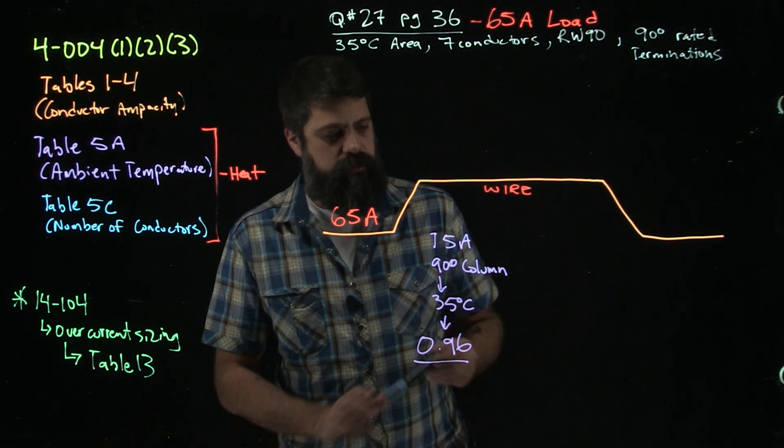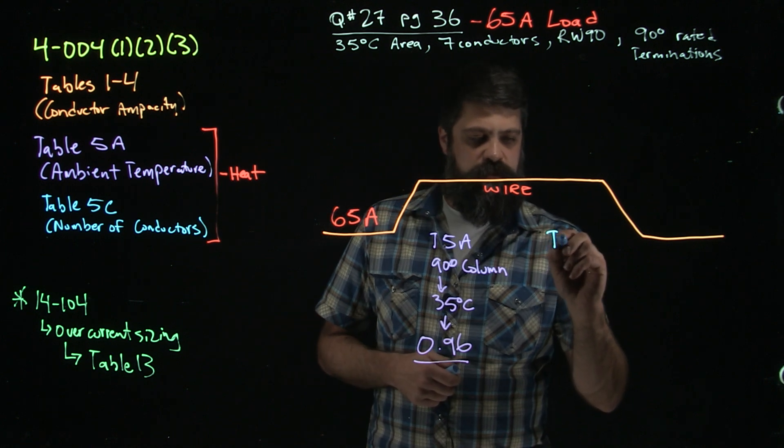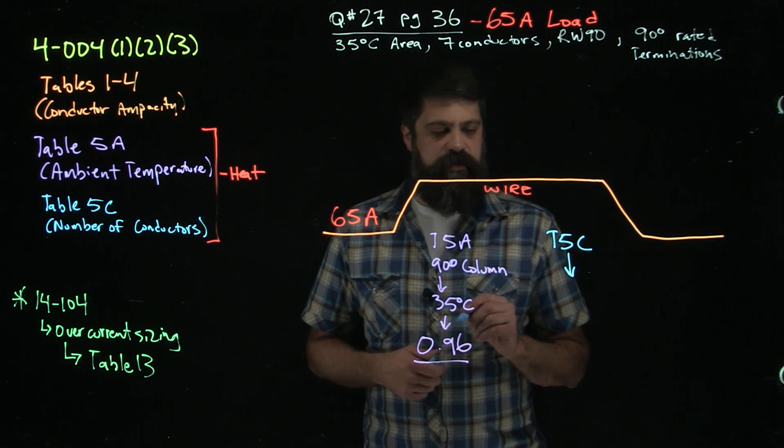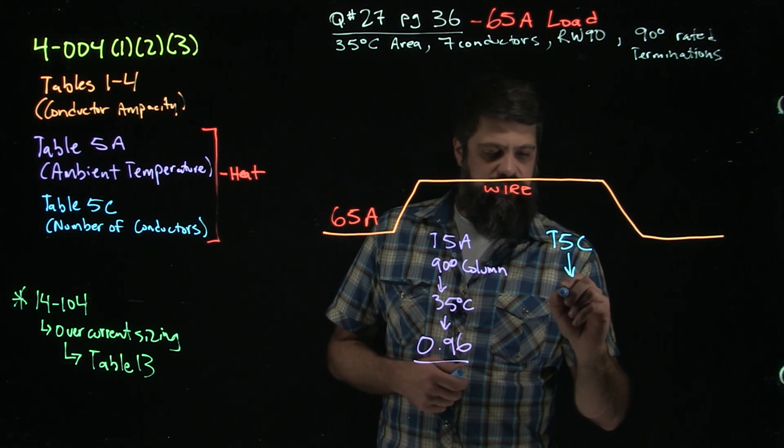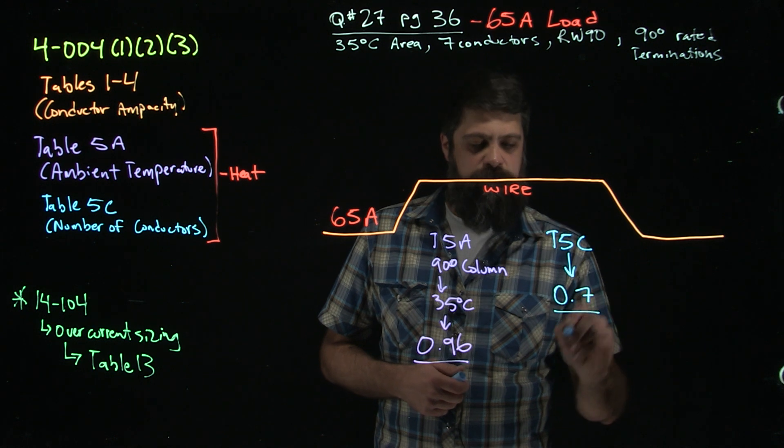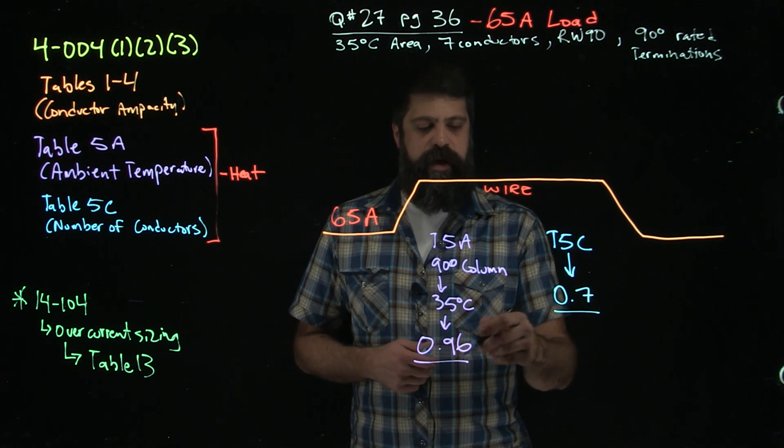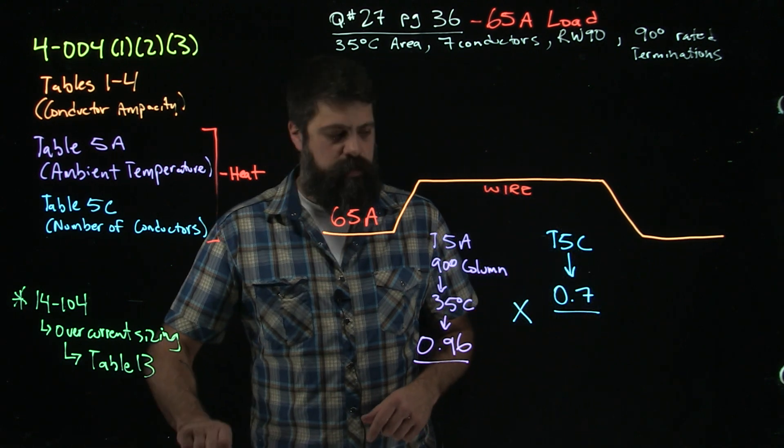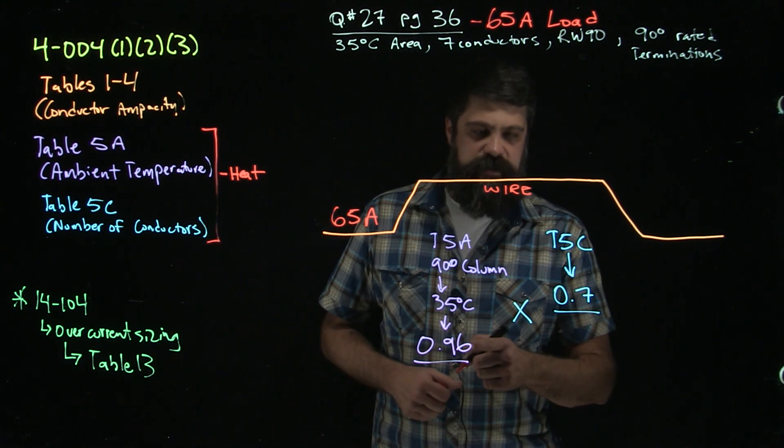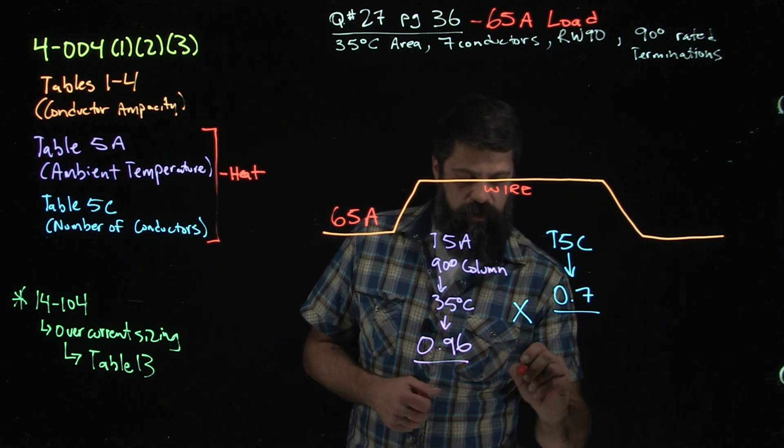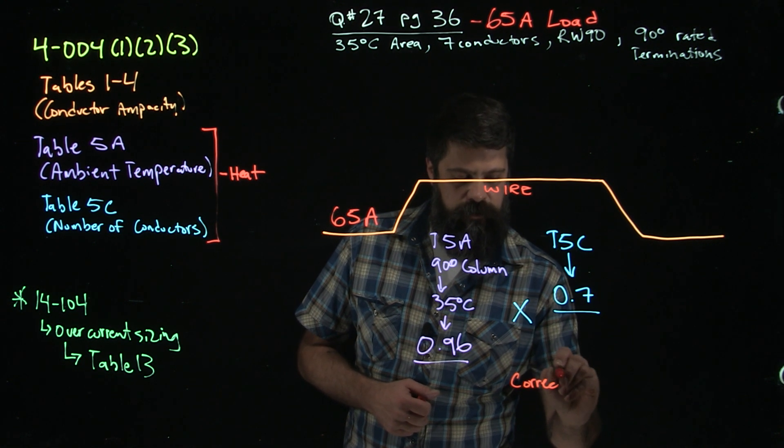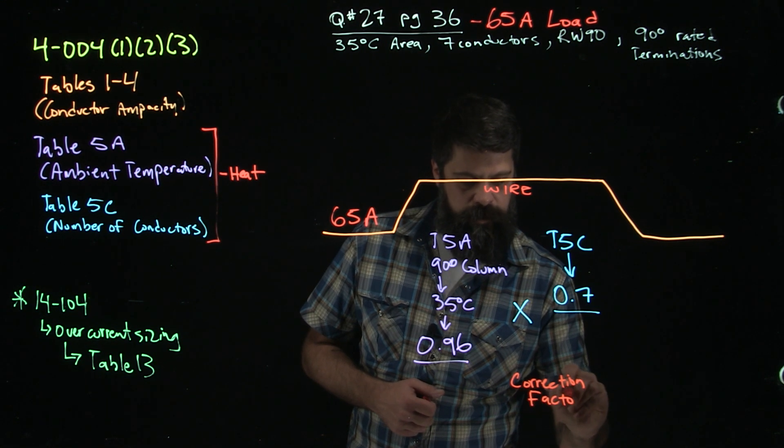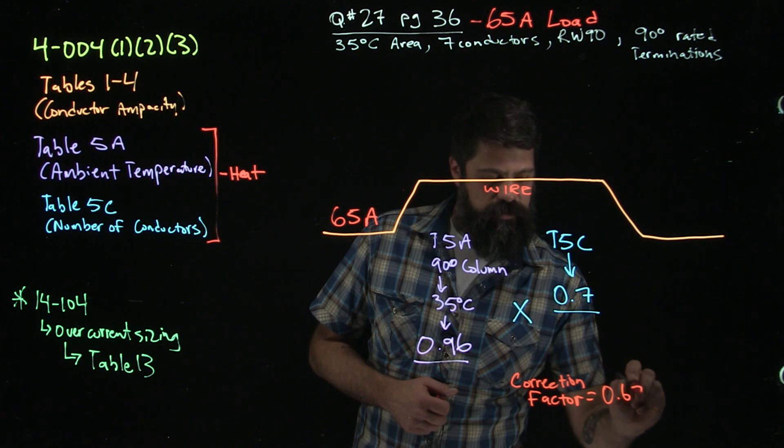Table 5C now just says how many conductors do I have. We look for that range, we find seven conductors, gives me a derating factor of 0.7. If I want to know the combined correction factor that I'm going to use for this overall, I'll multiply those two things together. 0.96 times 0.7 gives me an overall correction factor of 0.672.